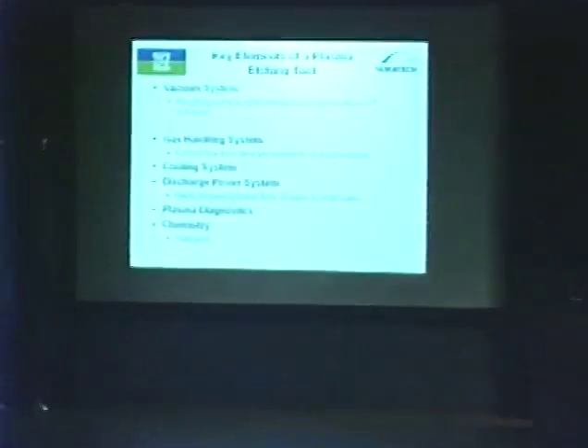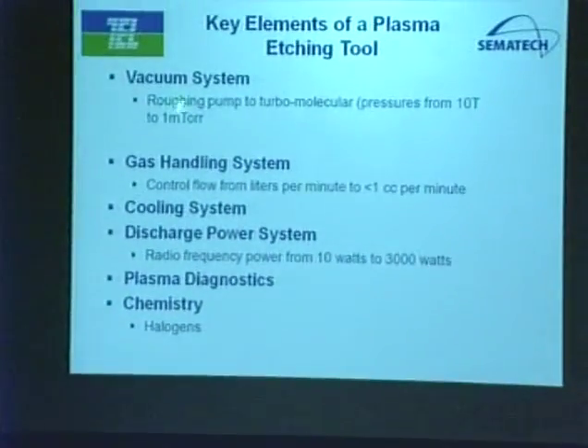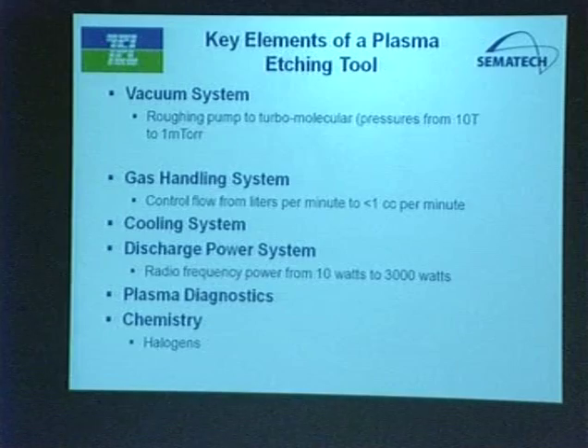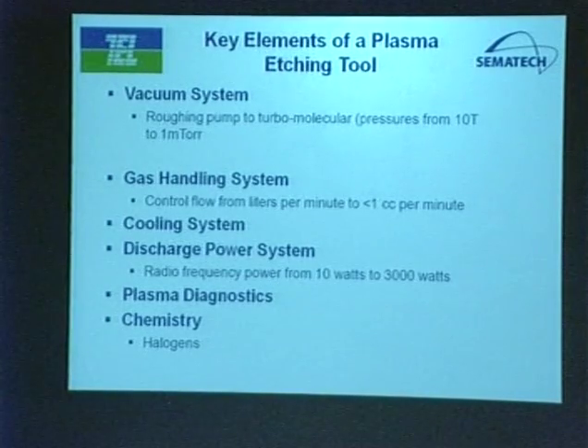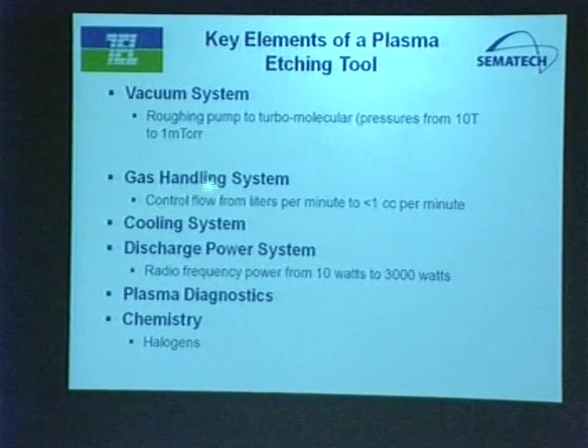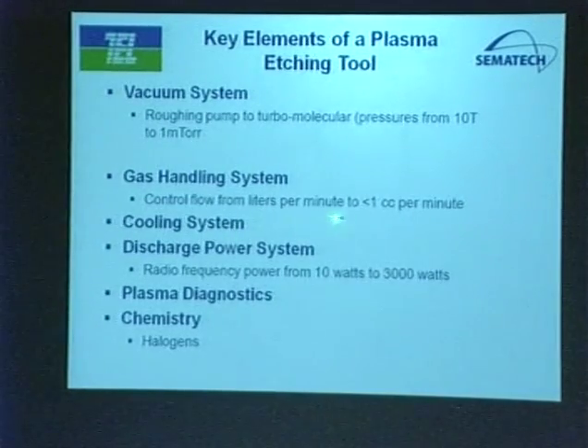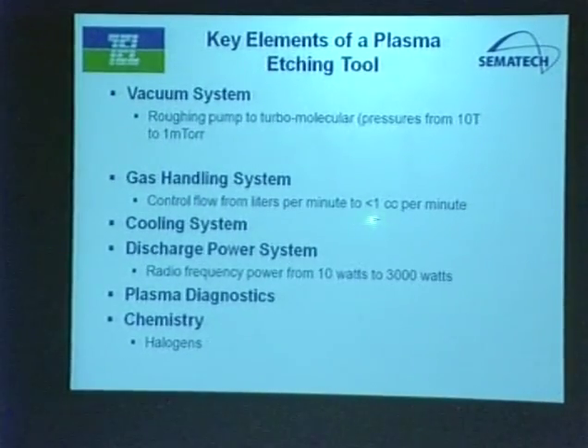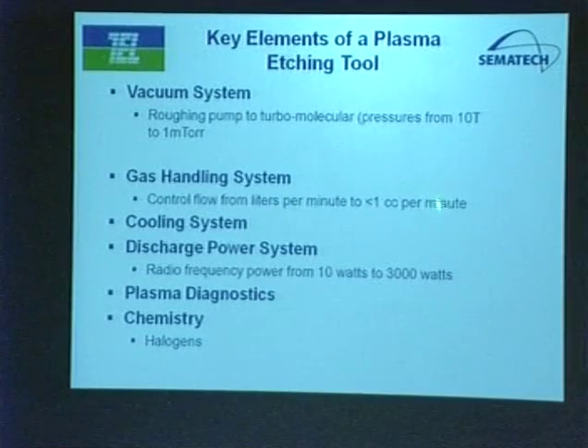I think we'll break it down into the individual pieces now to give you an idea of the simplicity of what goes on. I'm going to talk a little bit about roughing, or the vacuum system. There's roughing pumps, turbo pumps, pressure range. There's a gas handling system that we just talked a little bit about. This thing controls gas flows from liters per minute down to on the order of 1 cc per minute.